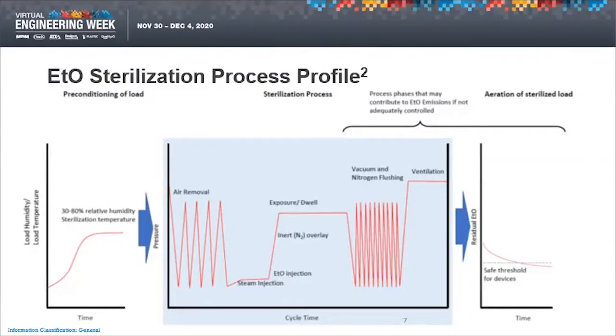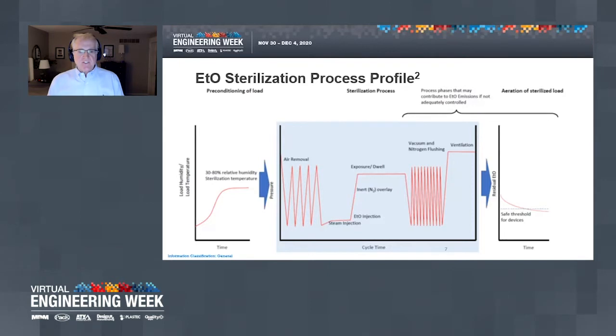Here's a graphic of a typical EO cycle that FDA presented at the November meeting that I really like if you're not really familiar with EO sterilization. This is a very good illustration of the many steps involved in the process. EO sterilization is a very complicated process when compared to, say, E-beam or gamma radiation sterilization. The typical EO cycle has around 100 process steps and can take anywhere from 20 hours to a few days to complete with aeration. What possibly could go wrong? In fact, it's really quite remarkable that these cycles run with those variables and these temperatures and these chemicals as reliably as they do. And it's really a testament to the great work the industry does to validate this critical process.